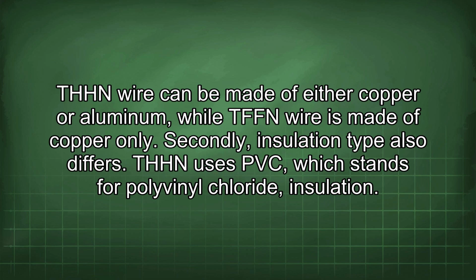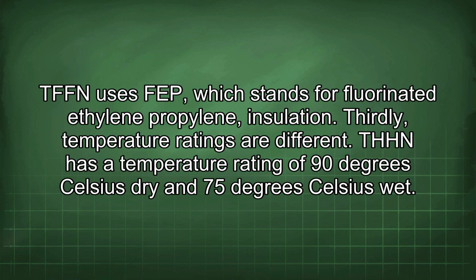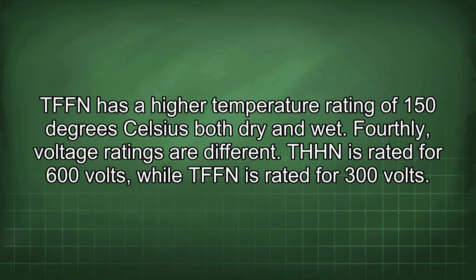Secondly, insulation type also differs. THHN uses PVC, which stands for polyvinyl chloride insulation. TFFN uses FEP, which stands for fluorinated ethylene propylene insulation. Thirdly, temperature ratings are different. THHN has a temperature rating of 90 degrees Celsius dry and 75 degrees Celsius wet. TFFN has a higher temperature rating of 150 degrees Celsius both dry and wet.